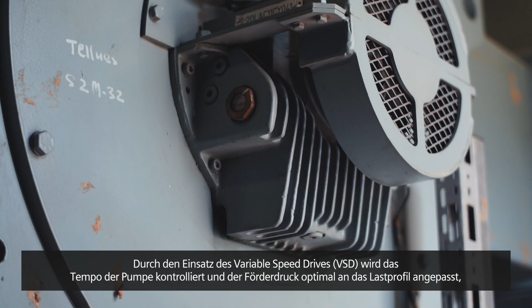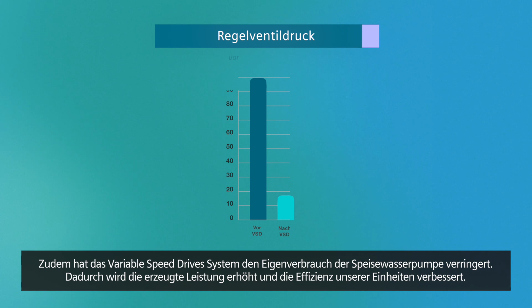The installation of this VSD project controlled the speed of the pump and modulated the discharge pressure optimally according to the load profile, delivering the required flow at a much lower motor power. The pressure difference across the throttle control valve has now been reduced from 100 bar to 20 bar. It has also reduced auxiliary power consumption of the feed water pump, thereby improving the generation output and efficiency of our unit.